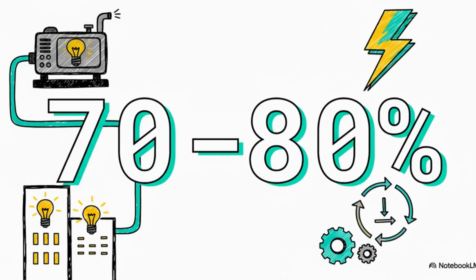And here's one last kind of counterintuitive piece of the puzzle: to keep them reliable for the long haul, these massive engines are actually designed to be run hard, ideally at about 70 to 80% of their full capacity. If you run them at very low loads for too long, it could actually damage the engine. So it's a machine that is truly built from the ground up for the worst-case scenario.